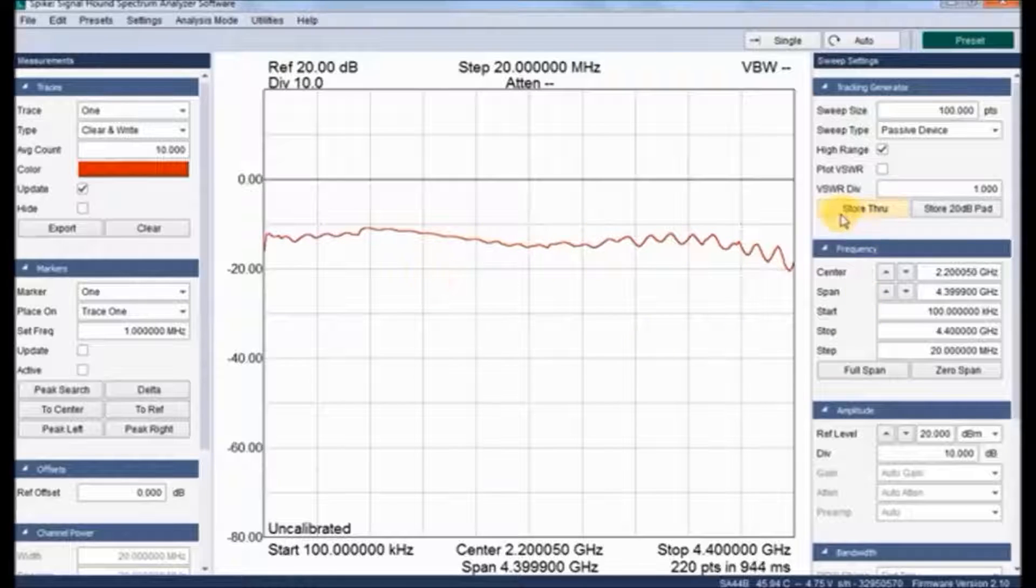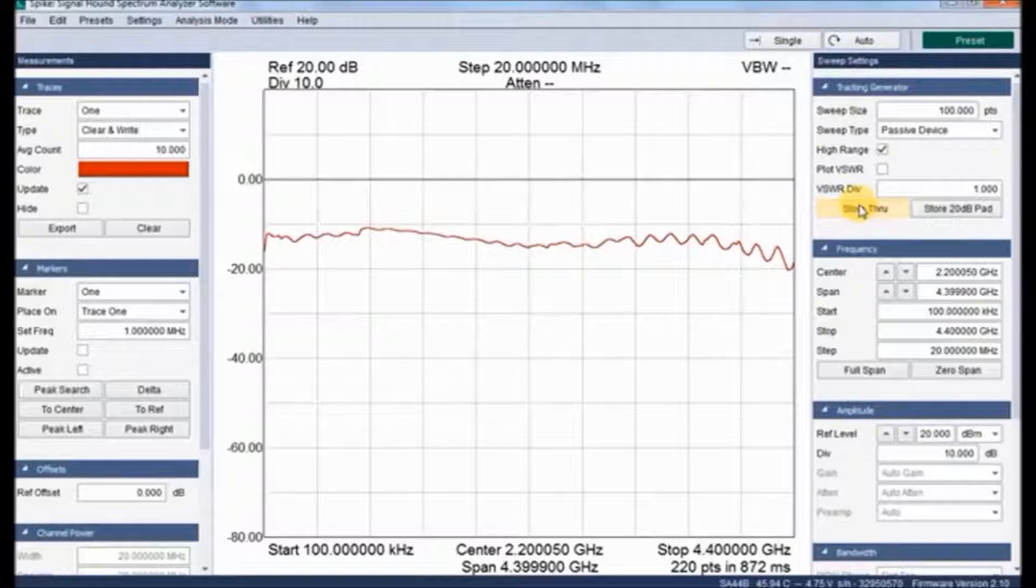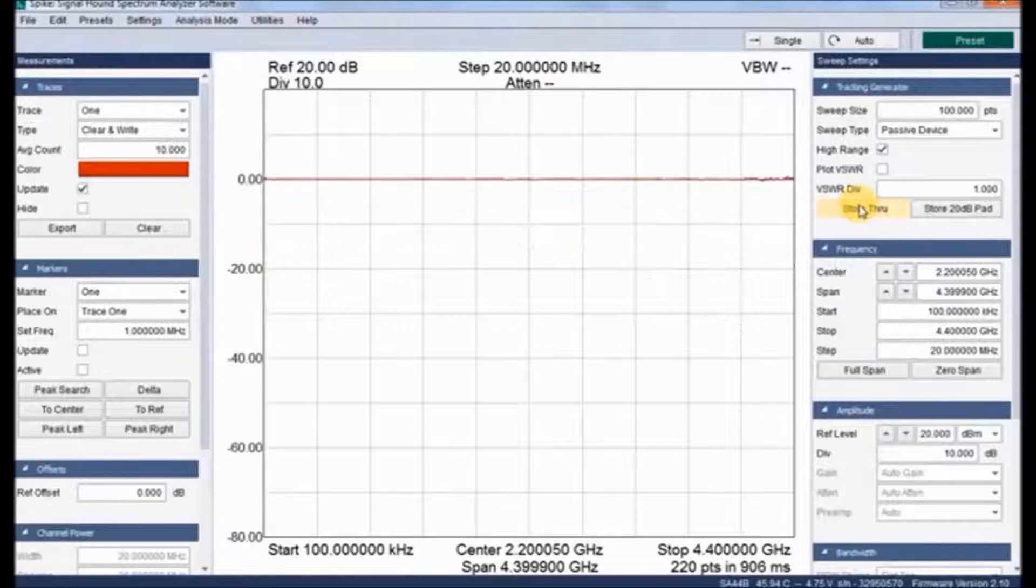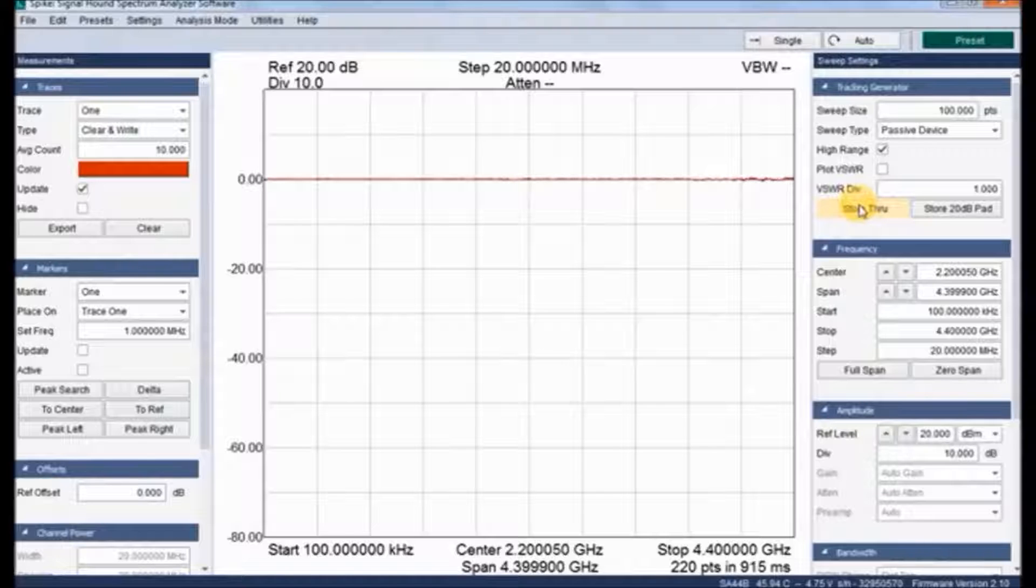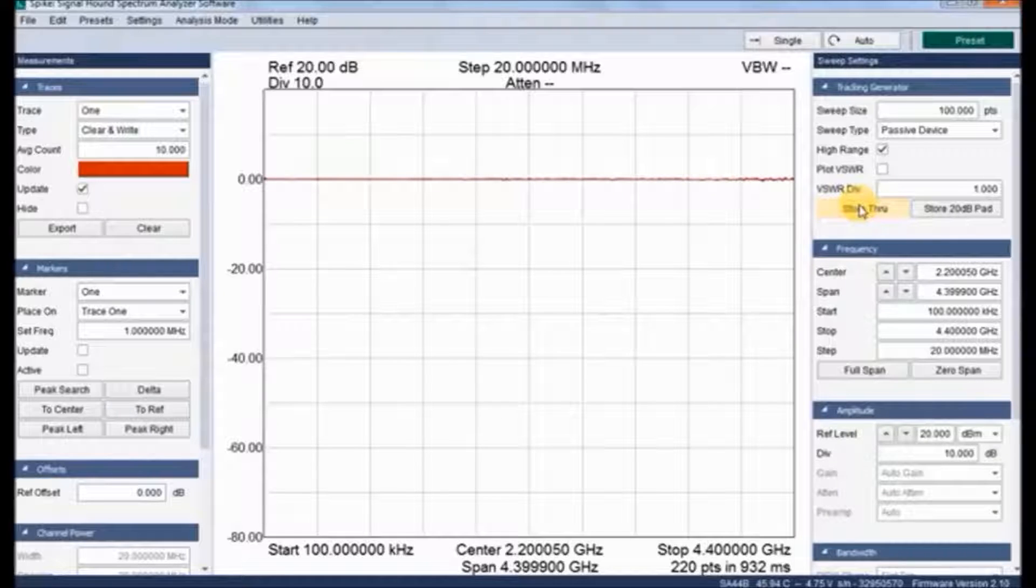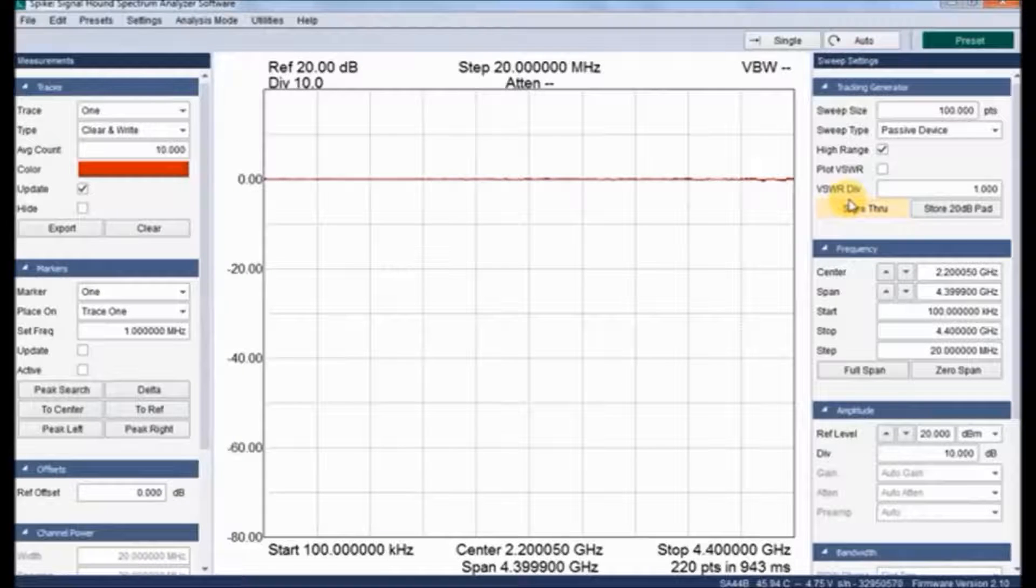And we need to calibrate by clicking store through. Here we have the option. Within a fractional second it calibrates and there is no loss occurring in the cable. After finishing it, let us connect the setup as shown in the beginning.